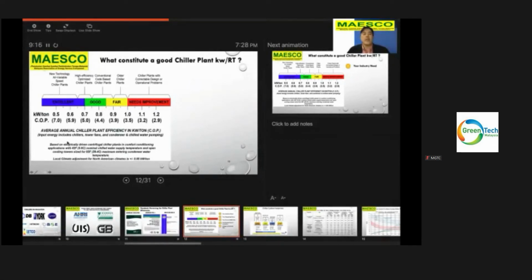Now, as you can see, what does this chart mean? This chart means the average annual chiller plant efficiency in kilowatt per ton, COP, which includes input energy, chillers, cooling towers, condenser, and chill water pumping. Now, in order for you to qualify under the excellent rating, you must go below 0.7 kilowatt per ton. That means when you add up your kilowatt for your chillers, for your tower fans, condensers, and chill water pumping, it is below 0.7. Now, this is how you select a very good chiller.